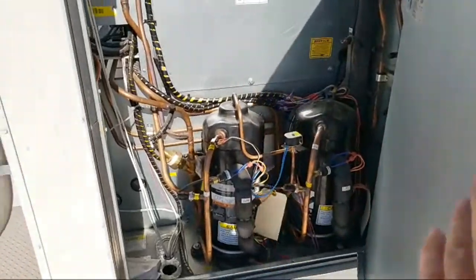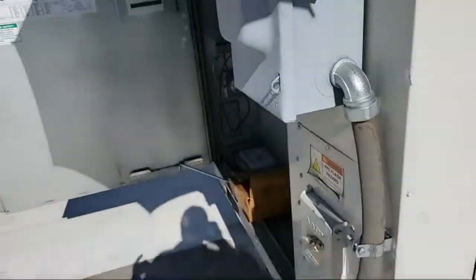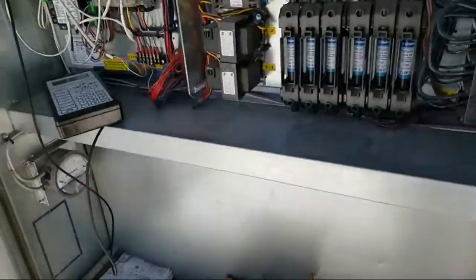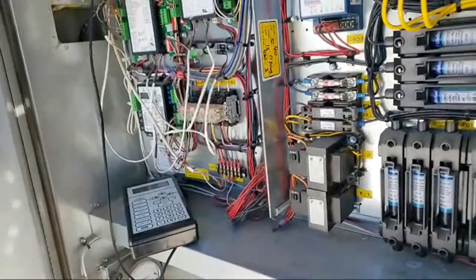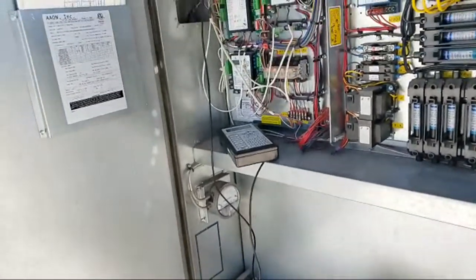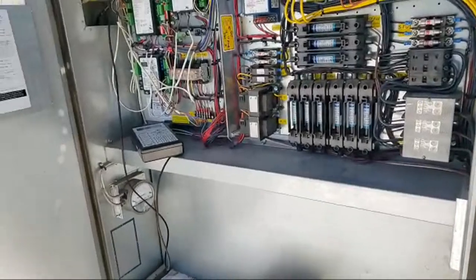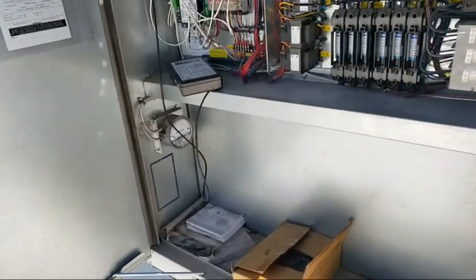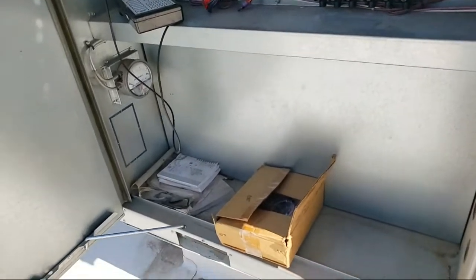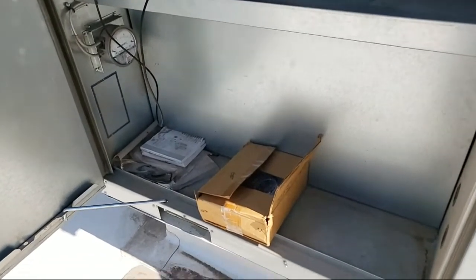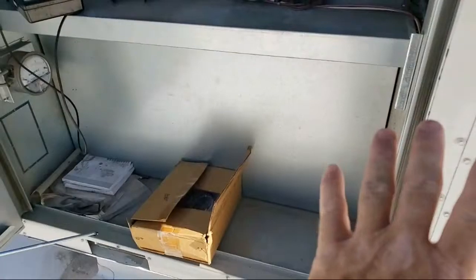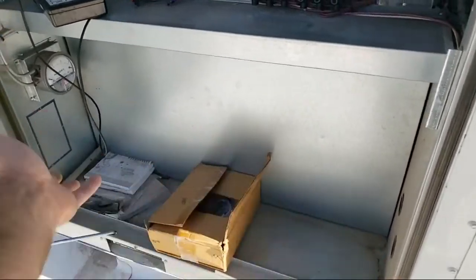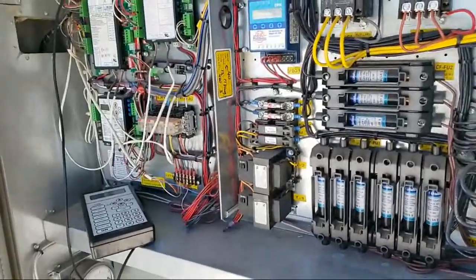But for some reason the unit's control is bringing on one or two compressors doing this thing, and it was overcooling while it was continuously trying to remove humidity. A lot of these units, if they're used to control temperature and humidity, like say in surgery rooms, also have a bank of electric heat right here with all the contactors and electronic controls for duty cycle that will add more heat, so the space temperature won't overcool. It'll control the supply air temperature. Well, this is just a server room, so they figure, hey, we don't need to install the heaters. It's just got that changeover valve and call it good.